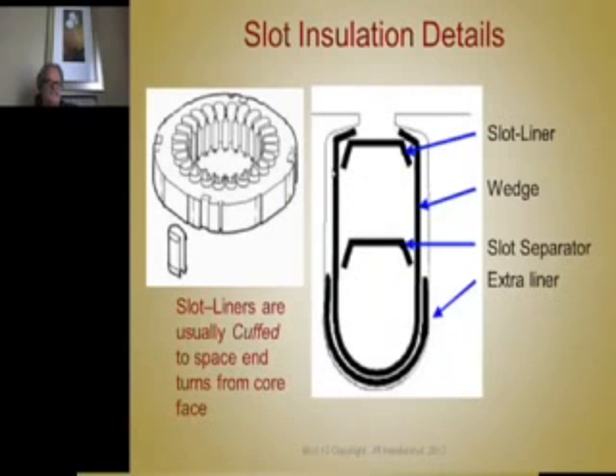Sometimes these slot liners are made long. Eliminate this, and you just overlap them, tuck them in here, and overlap them like this in the slot. It's very important when you're inserting coils in an insulated core like this that you don't get any conductors down underneath the slots. That happens frequently.